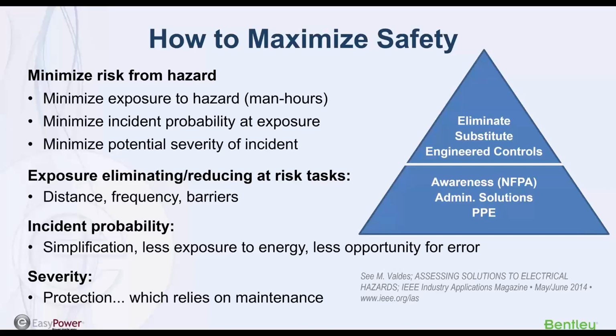Exposure is distance, frequency, barriers - we all kind of know what those are. Incident probability typically involves simplification of task, less exposure to energy, and less opportunity for error. If you're doing less maintenance that requires working on energized equipment, there's less opportunity for error. Every time you touch equipment, there's a possibility for human error that sets up a future problem. So as much as maintenance is important, too much maintenance may also be a risk - you need to figure out the right amount. Severity, of course, is protection, which relies on the maintenance of whatever is providing that protection.